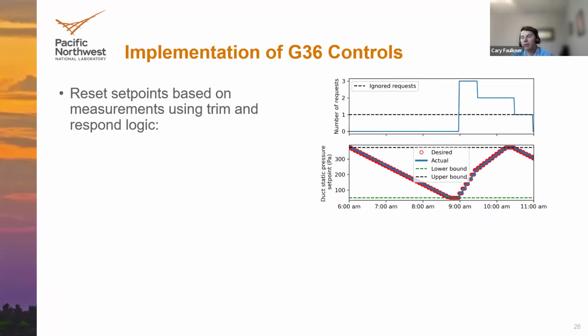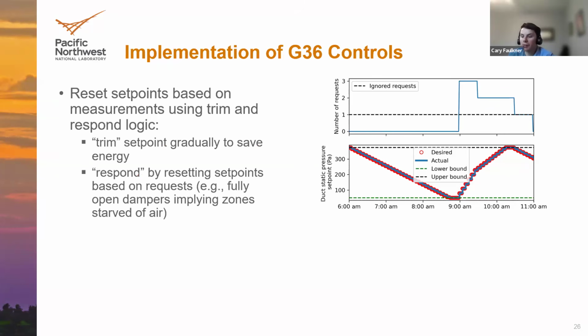The key aspect of these controls is that they reset the set points using system measurements from the building, and they reset them using trim and respond logic. So the idea here is you want to trim the set point in a way that's going to gradually save energy. You're not going to aggressively change the set point, but maybe slowly trim it, and then check on measurements to make sure that you can continue to trim in order to save energy. And then you might respond by increasing or decreasing your set point, depending on what the set point is, based on requests, these measurements from the zones.